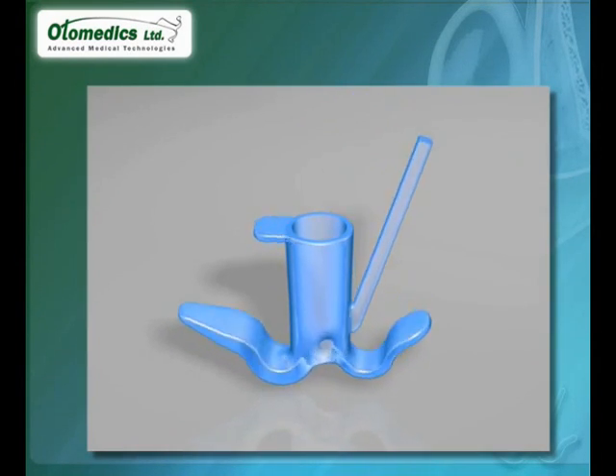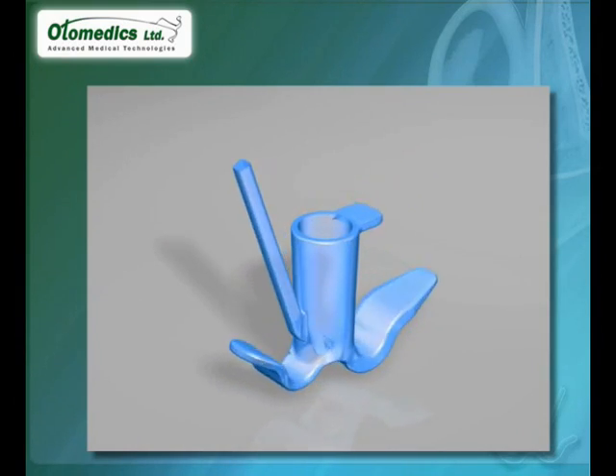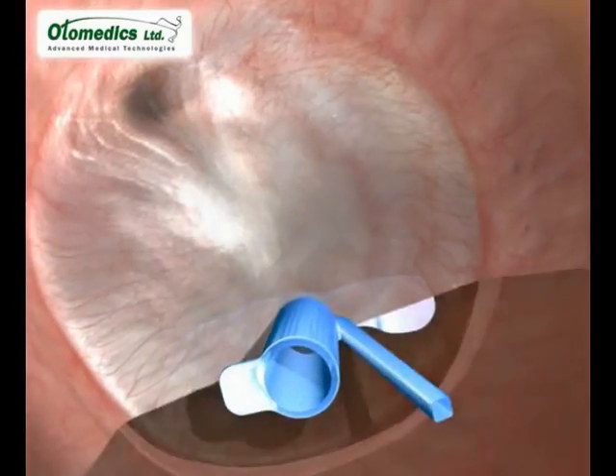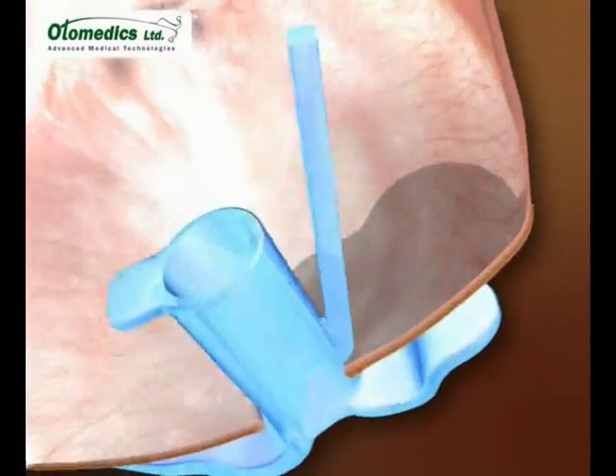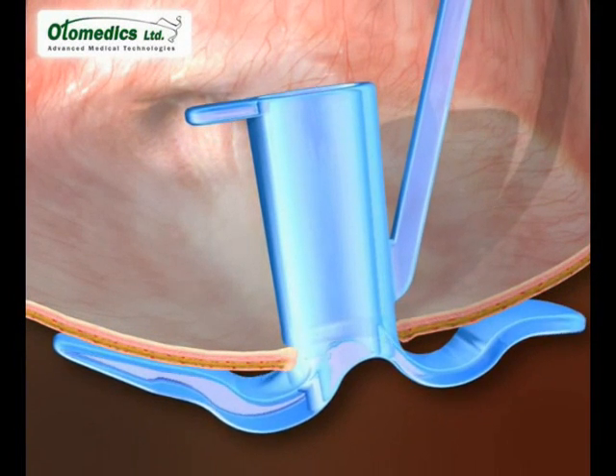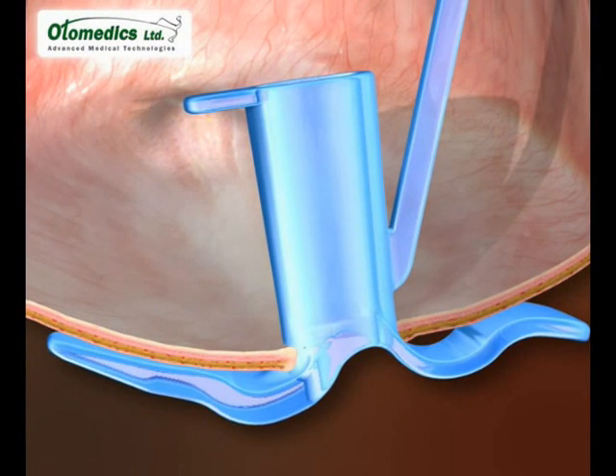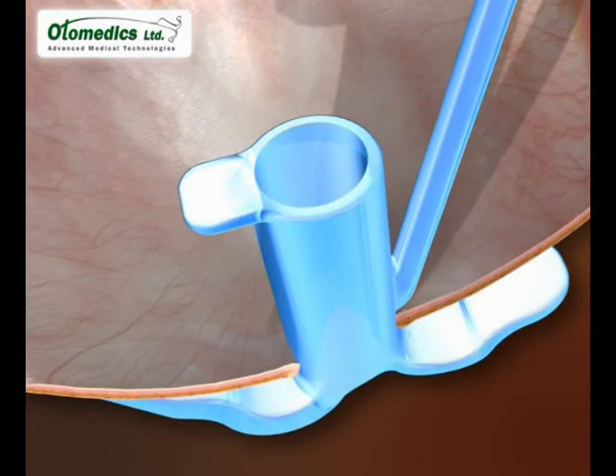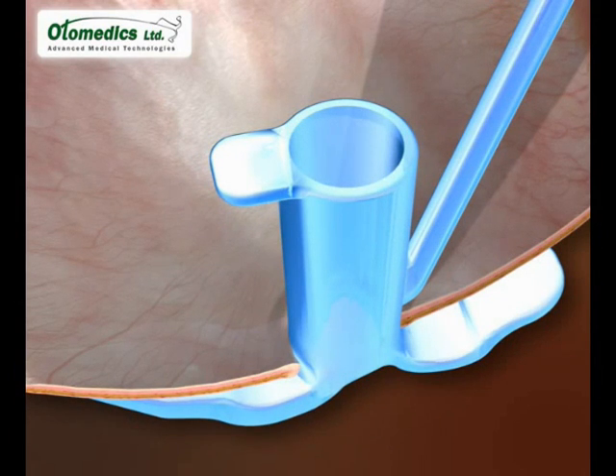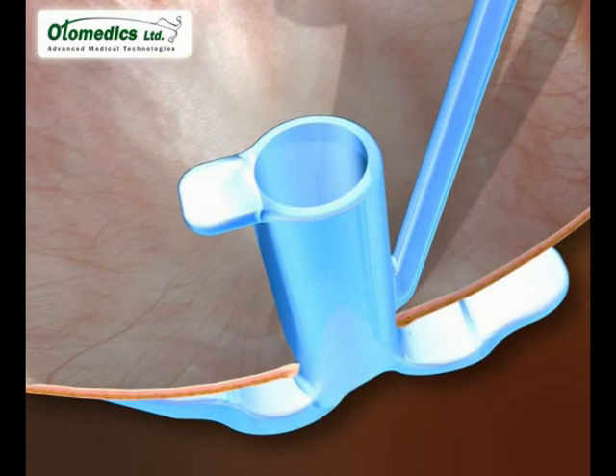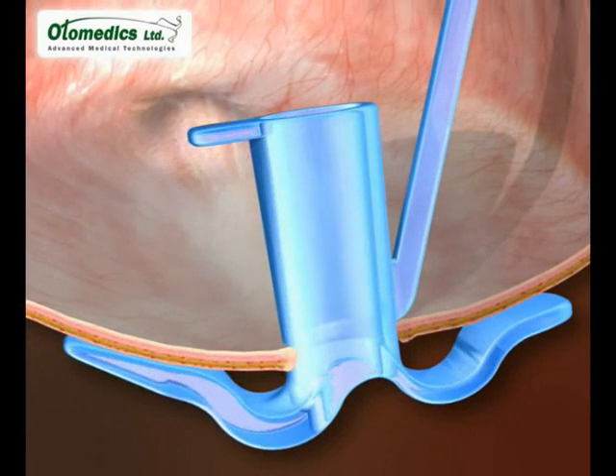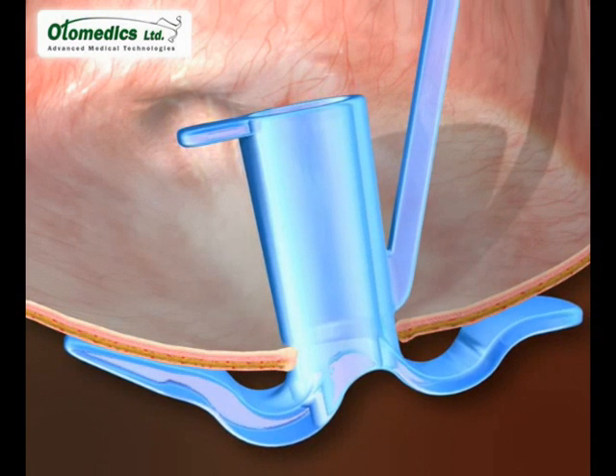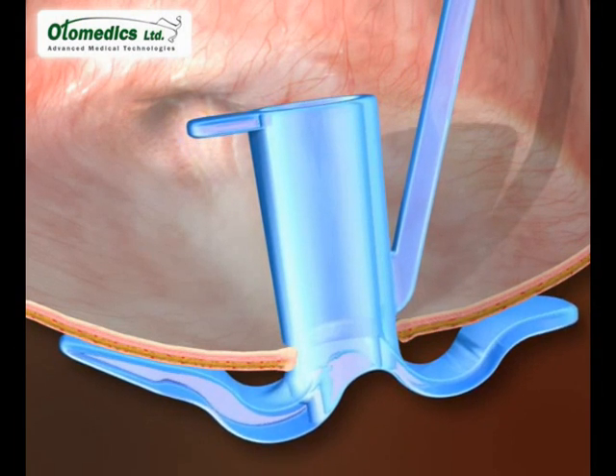Presenting the newly designed tympanostomy tube from Otomedics. This soft silicone tube is designed to contact the eardrum at some distance from the rim of the perforation, so as not to interfere with the blood supply of the rim. The lumen of the shaft is conical, allowing easy cleaning of clogs, and its flexibility enables repositioning after cleaning. It has a thick anterior arm that resists natural extrusion and a collapse mechanism activated by pulling the extraction handle and rotating the tube on its axis during extrusion.